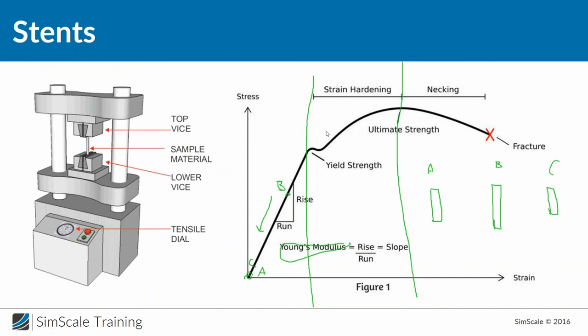When we design a stent, the idea is that inflating it will bring us into the plastic deformation region, so that we have a permanent deformation of the stent. We also want some hardening to give the stent higher stiffness. So when designing a stent, our aim is that at the final stage of inflation we are at the start of the strain hardening area — we have plastic deformation and hardening — but not too much strain, because we don't want necking.